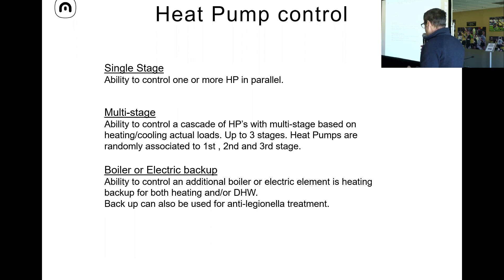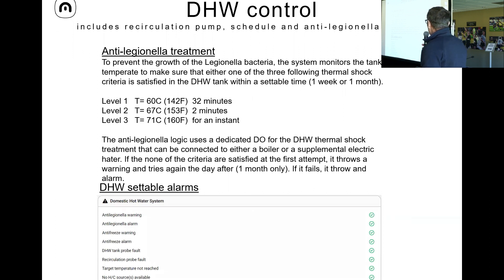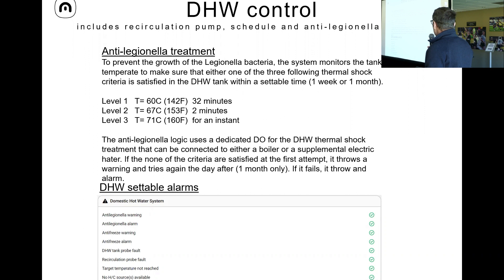We can also control a backup for heating — either a boiler or an electric backup. This is particularly useful when doing domestic hot water with a heat pump, and also for anti-legionella treatment, which kills the legionella bacteria. The anti-legionella treatment is based on three different criteria of temperature and how long the temperature is held. These three criteria kill the legionella bacteria and can be done every week or every month — here in New Zealand it's required to be weekly.